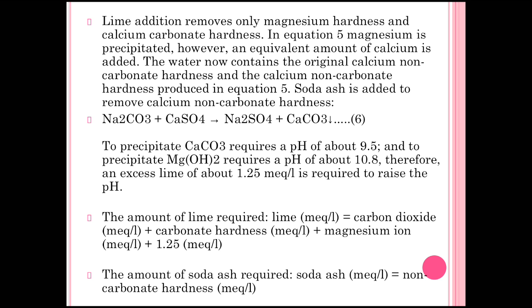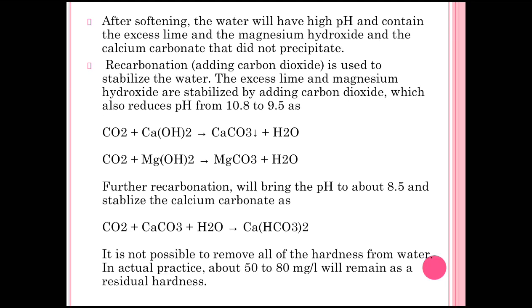The amount of lime required (in meq/l) equals: CO₂ (meq/l) + carbonate hardness (liters) + magnesium ions + 1.25. The amount of soda ash required equals non-carbonate hardness (meq/l). After softening, the water will have high pH and contain excess lime, magnesium hydroxide, and calcium carbonate that did not precipitate. Recarbonization — re-addition of CO₂ — is used to stabilize the water; excess lime and magnesium hydroxide are stabilized by adding CO₂, which reduces pH from 10.8 to 9.5, and CO₂ + Ca(OH)₂ gives CaCO₃ precipitate.